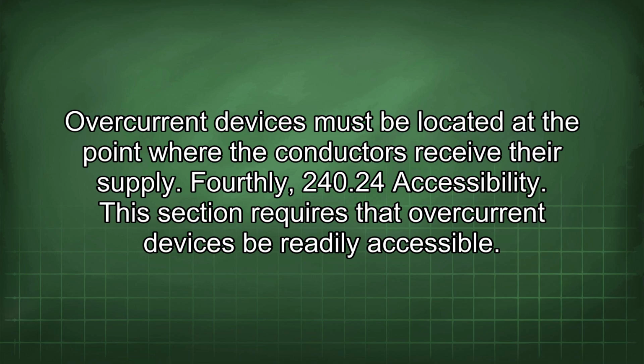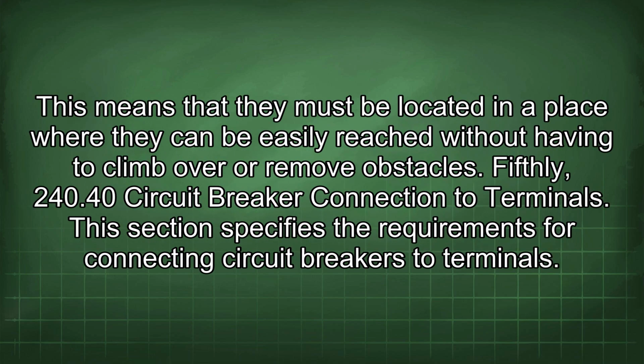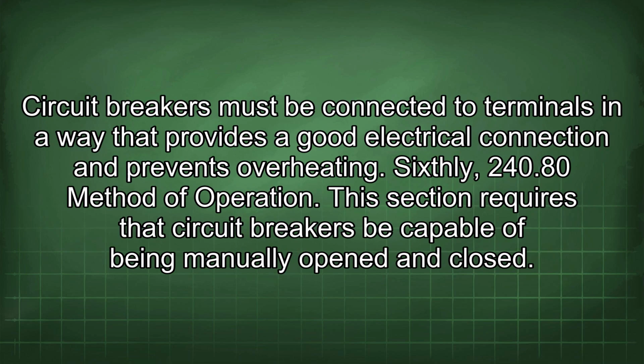Fourthly, 240.24 Accessibility. This section requires that overcurrent devices be readily accessible. This means that they must be located in a place where they can be easily reached without having to climb over or remove obstacles. Fifthly, 240.40 Circuit breaker connection to terminals. This section specifies the requirements for connecting circuit breakers to terminals. Circuit breakers must be connected to terminals in a way that provides a good electrical connection and prevents overheating.